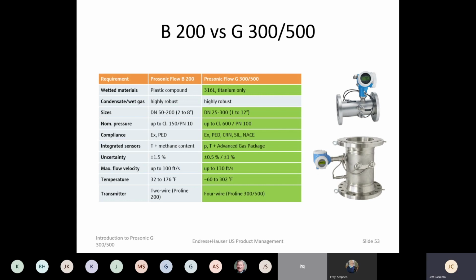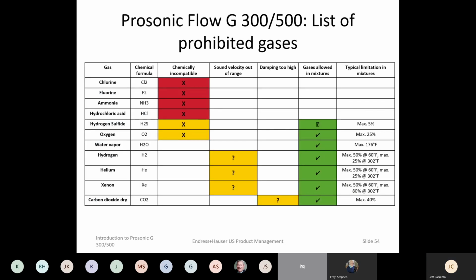The ProSonic B200 is the meter we use for biogas. That's a 2-wire meter that also offers methane content output. And then the ProSonic Flow G300, 500 is all stainless steel with titanium sensors and higher pressures. Some of the gases we can't do: chlorine, fluorine, ammonia, and hydrochloric acid gas, because they are corrosive and we're just not compatible chemically. And then the sound velocity is out of range in hydrogen, helium, xenon, but most other gases or a lot of mixtures we can measure with ultrasonic meters.